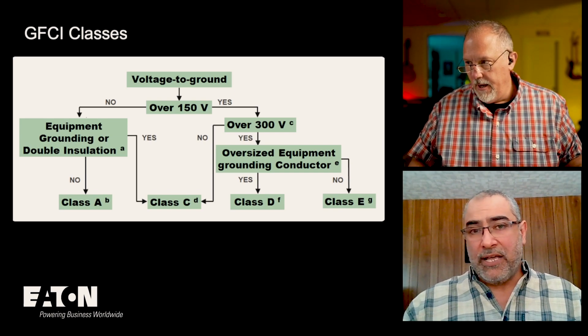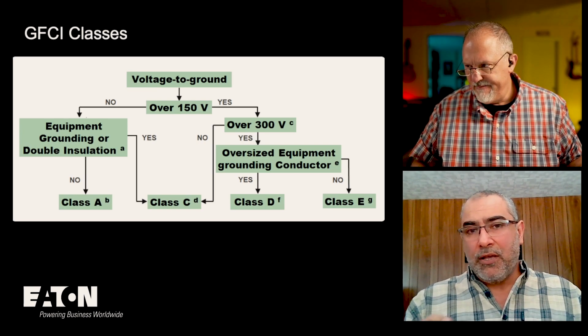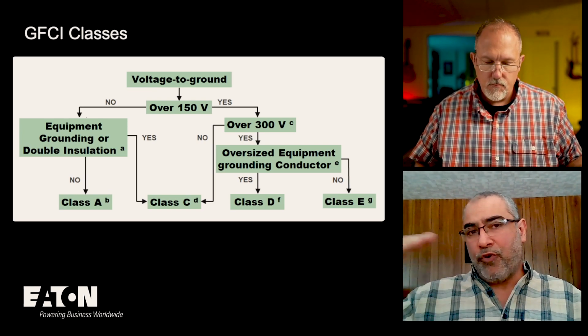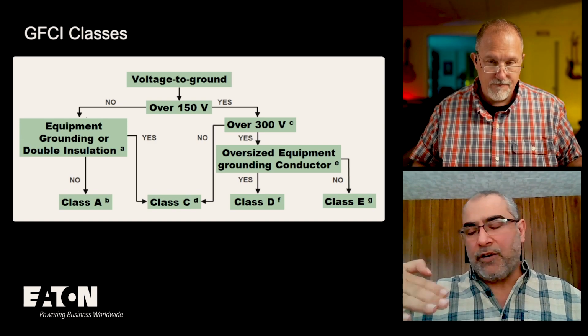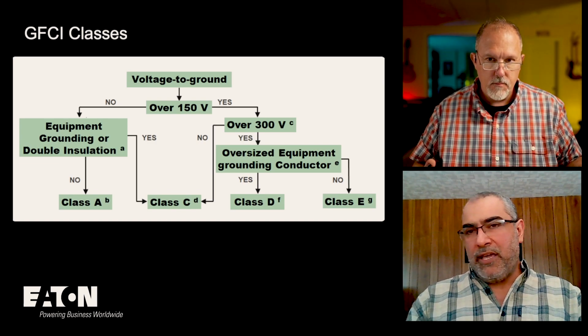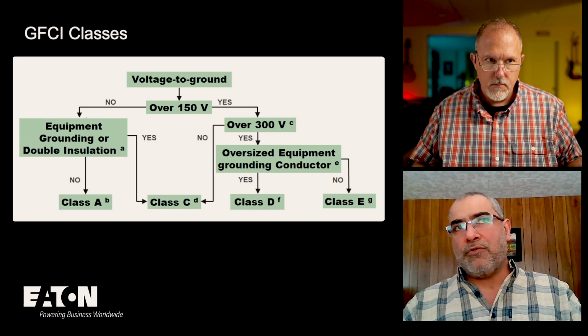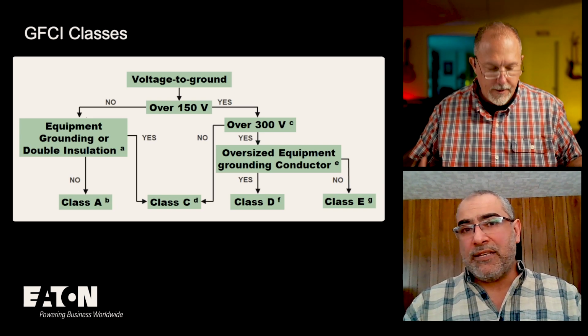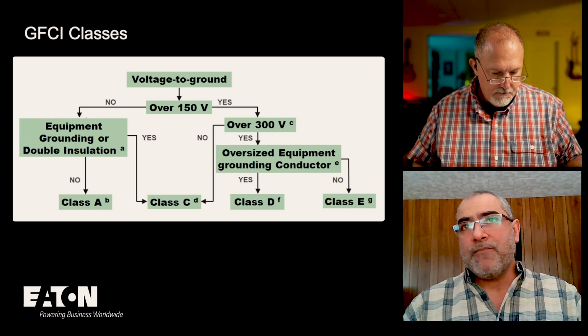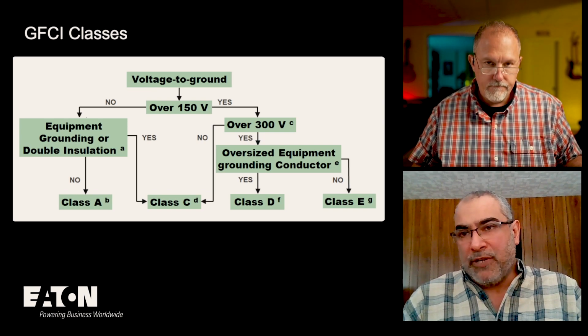One thing we haven't mentioned is that class C, D, and E, because of the higher voltage required and higher trip levels, require 20 milliamps. They require what UL calls ground monitor and interrupt, which means those devices are required to monitor your equipment grounding conductor.